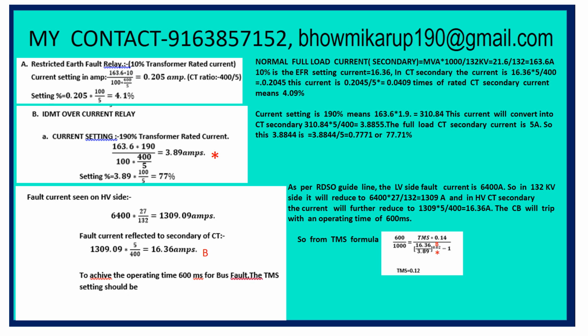So you have seen the current setting and percentage relay current of the earth-fault relay. Now we will do the overcurrent relay IDMT, inverse definite minimum time lag. It means our traction transformer has the capability to bear overload and is designed for 200% overload, but it will permit it for a certain time.